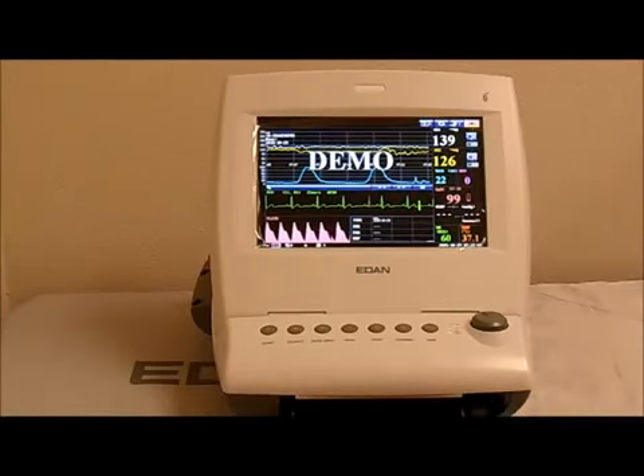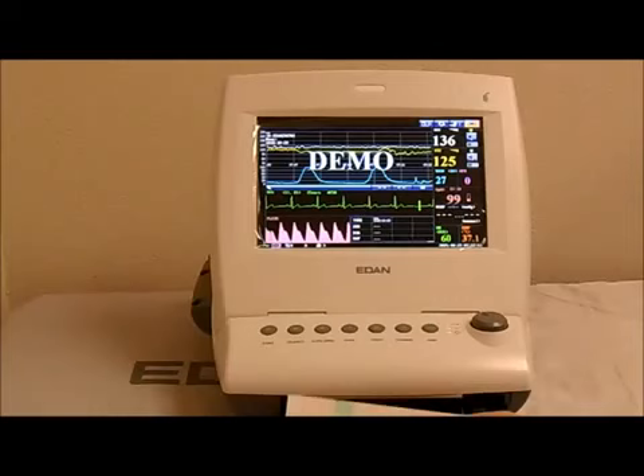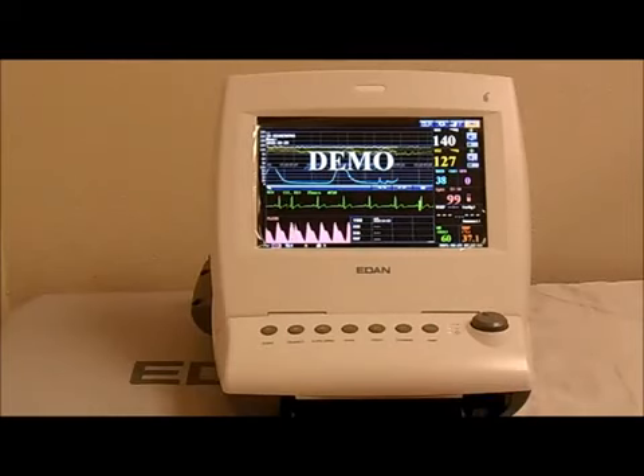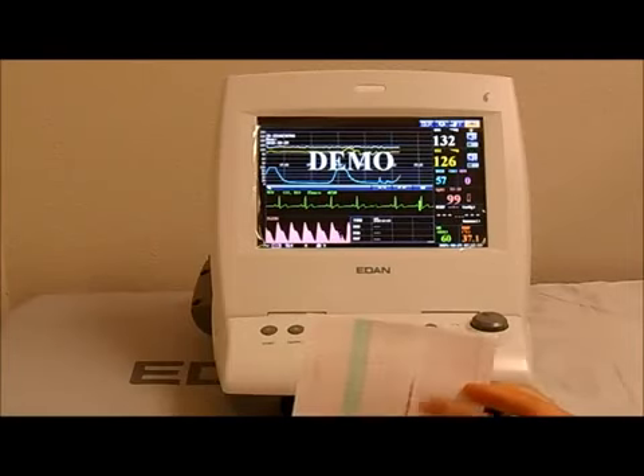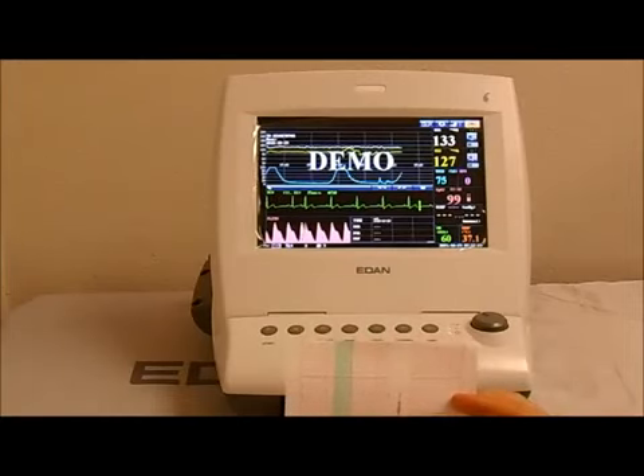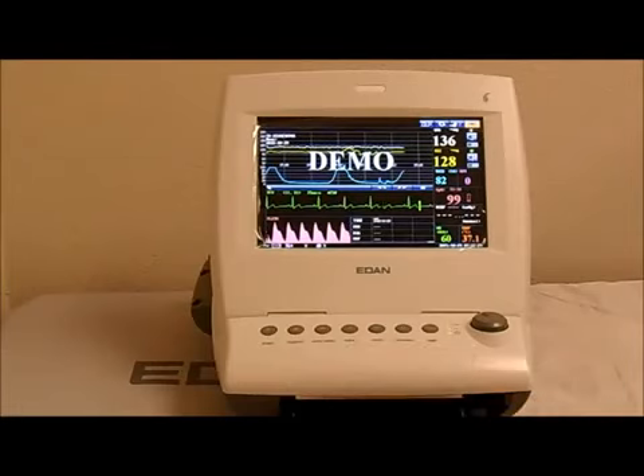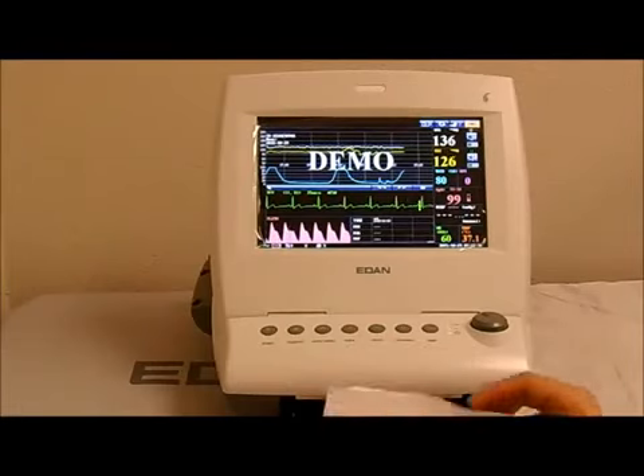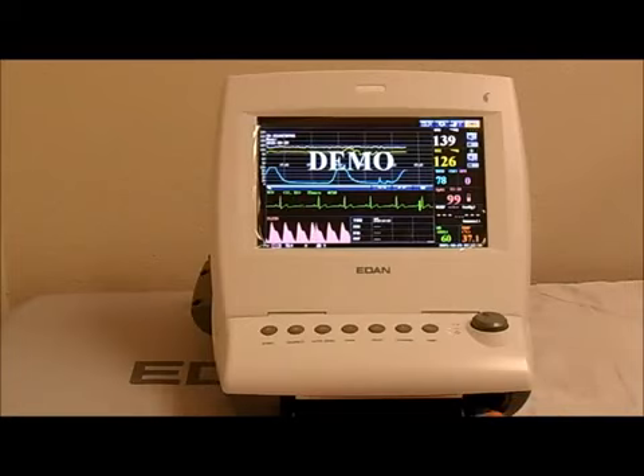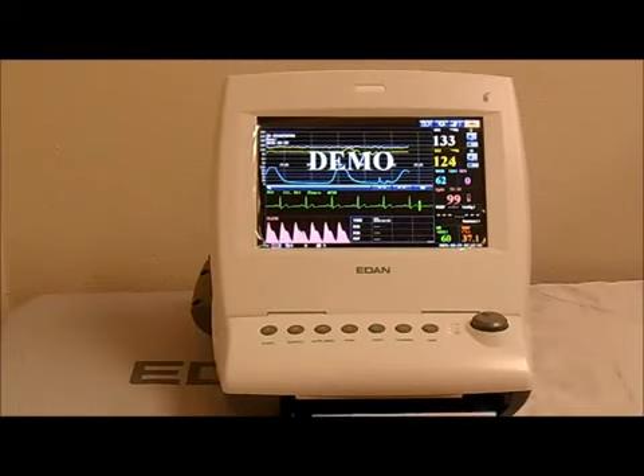Now, to load the paper, you want to make sure you have the grid facing up. And if you take a look at the opposite side, one of the sides is going to have a red marker. This is the indicator to assist the clinician to know that the paper is about to run out. So you want to make sure that you're starting and loading the paper on the side that doesn't have that red marker. So when you place the paper, the FHR reference has to be on the left side.